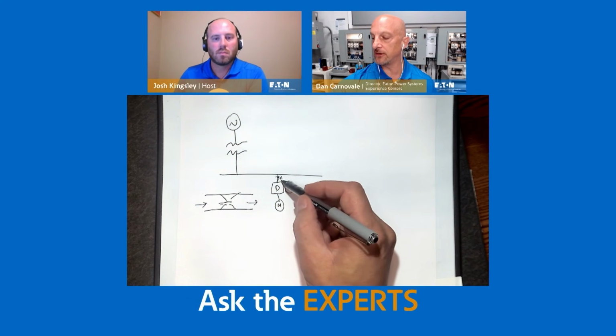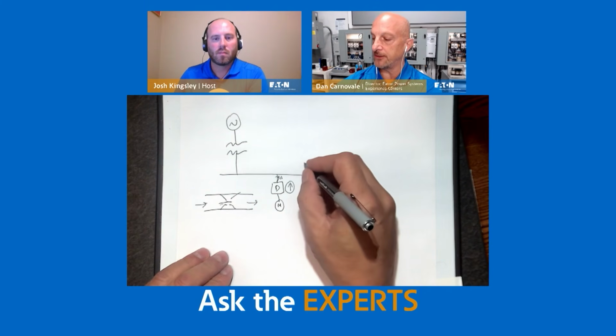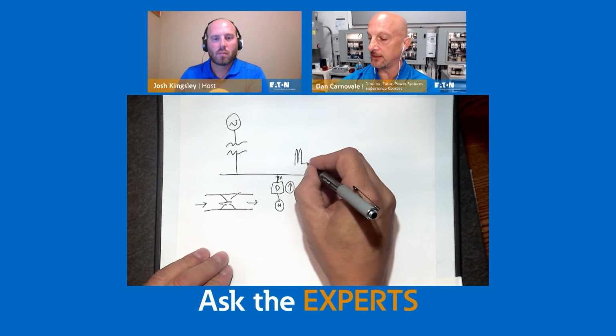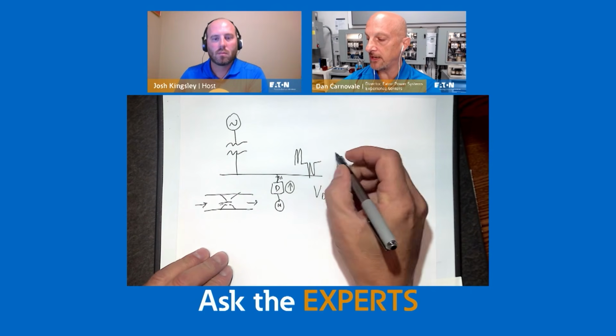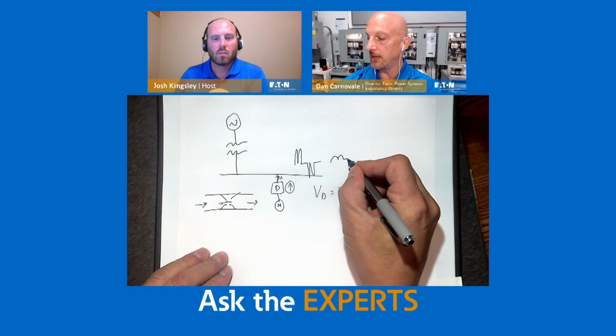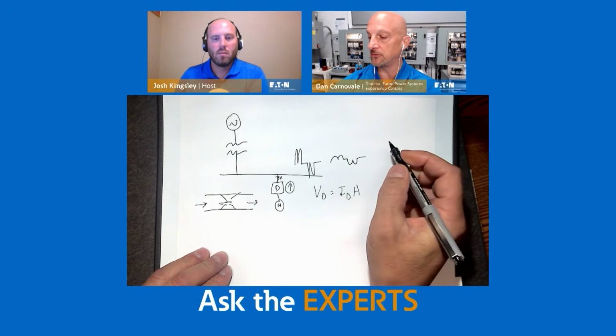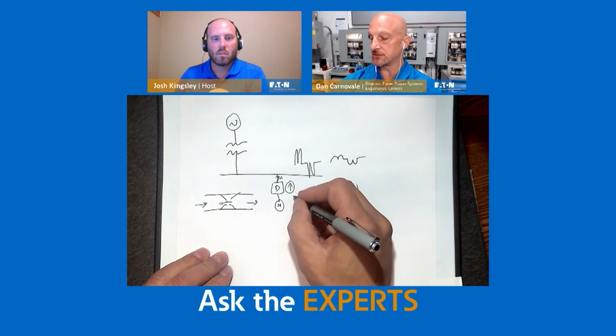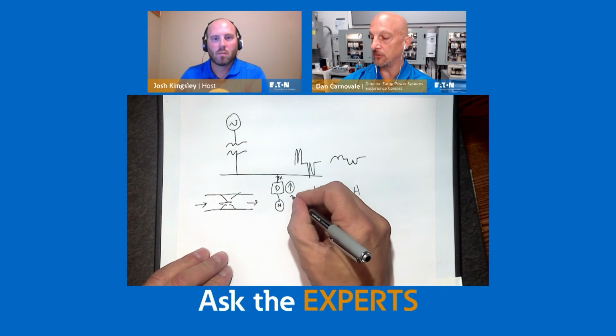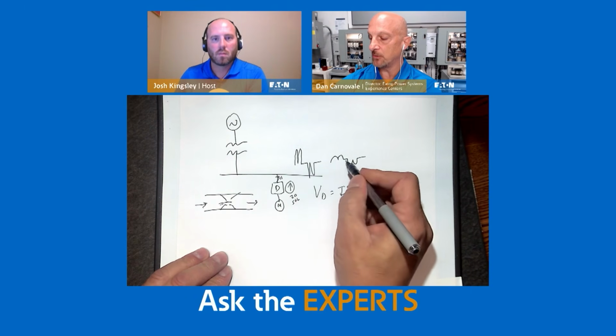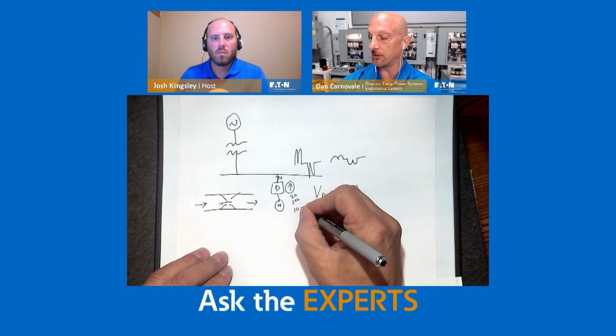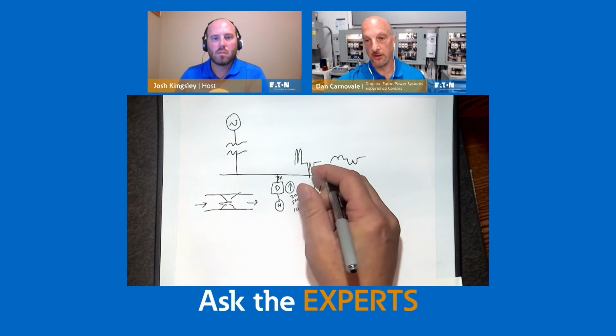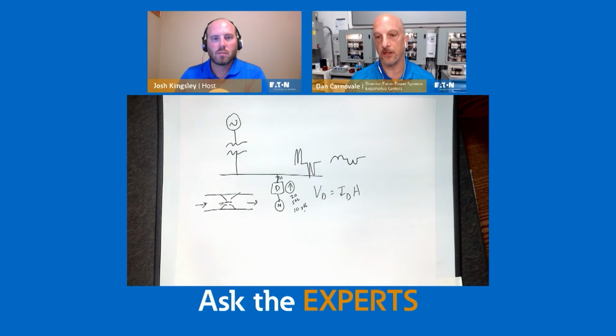So by putting a drive here with a line reactor or a DC choke built in, we take a current that looks something like this, and we end up having a current that looks more rounded off. And the harmonic pattern associated with that is much less. In other words, we have a lot less distortion. So if in the first case we didn't have a reactor, we had 20 amps of, say, fifth harmonic current, with the second case we might have 10 amps of fifth harmonic current, and that is probably the least expensive version of things. Our drives, our DG1s for example, and our other variable frequency drives have DC chokes built right in, and 5% is kind of the right number for that.